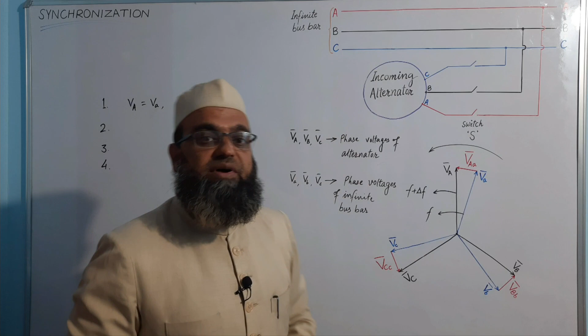And the last one, the fourth one, phase displacement between the phase voltages of incoming alternator and infinite bus bar must be zero. I am talking about phase displacement. That is, the two phasors must have same phase angles. For example, see the condition. At this moment, if we are going to close the switch, though the magnitudes will be same, the two phasors are having a finite phase displacement.